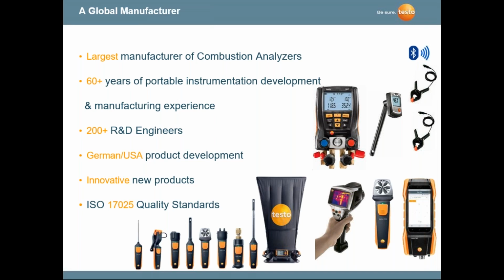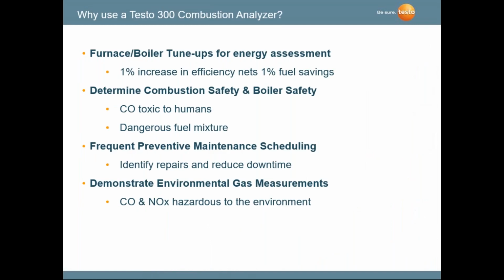And why I'm bringing this up is because with combustion analyzers, it's all about the accuracy of the sensors, the oxygen sensor, the carbon monoxide sensor, and other sensors that we use, and you can rest assured that your instruments are calibrated at Testo before they leave the factory under certain quality standards that maintain the accuracy of these instruments.